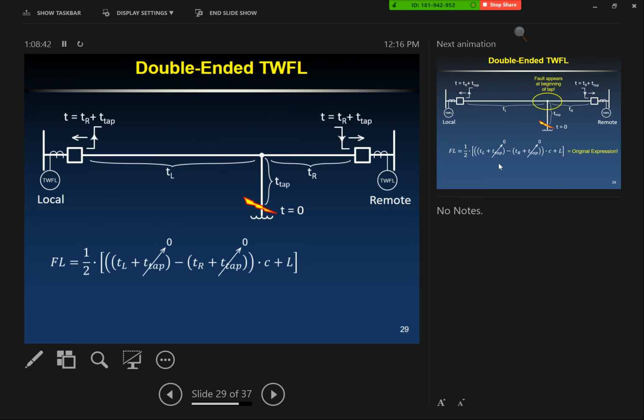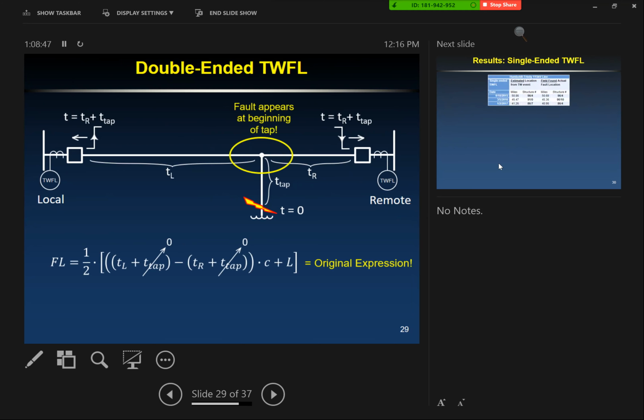So doing a double-ended method, everything's going to appear to be right at the beginning of the tap. It doesn't matter where it happens along this line, your double-ended method is going to say it's right there. And you just have to know to interpret that, hey, it's telling me it's right at the tap. All I can tell from this double-ended method is the tap. You might then try to use your single-ended method, if it works out for you, if they sectionalize and test it and it's a clean enough event, to actually give a better answer. So your single-ended has at least the possibility of giving you more information than this double-ended method for taps.